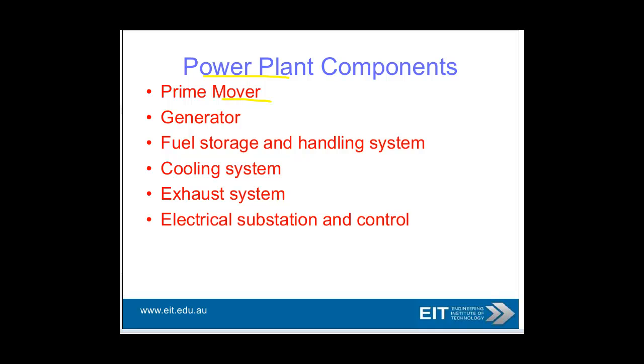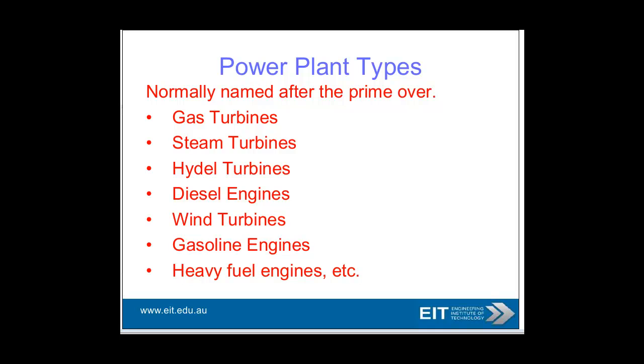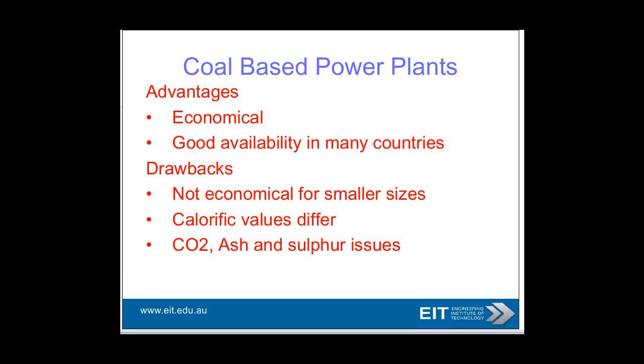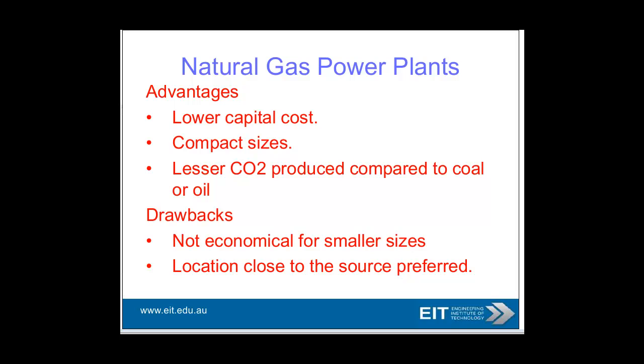Power plant components are the prime mover, the generator, fuel storage and handling system, cooling system, exhaust system, and substation and control. The types of power plant range from steam turbines all the way through to wind turbines and heavy fuel engines, so it's quite a wide range. Coal-based plants are economical, but very bad for the atmosphere. Natural gas has lower capital cost, but is not economical for smaller sizes.